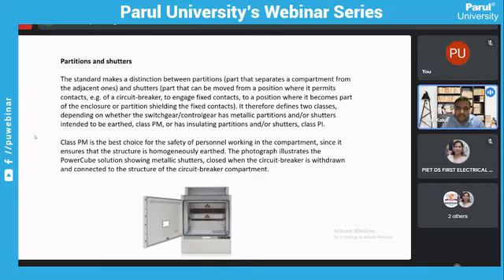Now, these are just some bits of partitions as well as shutters. So whenever we are racking out any circuit breaker out of the compartment, there are shutters which slide above and below and close the live contacts. In that case, there are also padlock provisions provided in the switchgear so that any operator or technician doing any maintenance activity, specifically in this bus bar compartment, after withdrawing the circuit breaker, does not accidentally touch any of the live connection joints there, against which our breaker jaw contacts will be sliding and making the circuit. So it will have a complete metallic partition, and there will be sliders, and those sliders also can be padlocked.